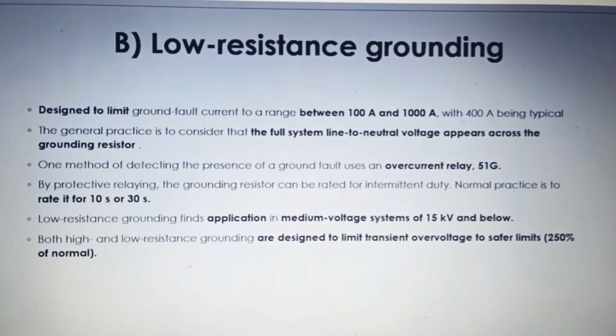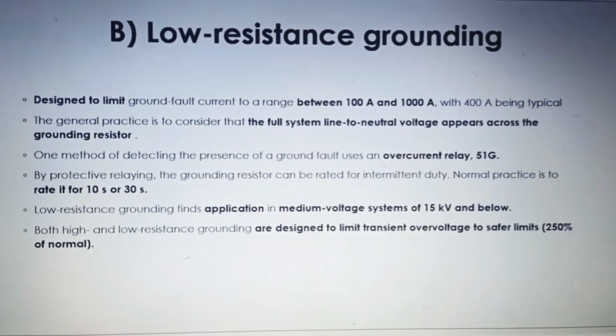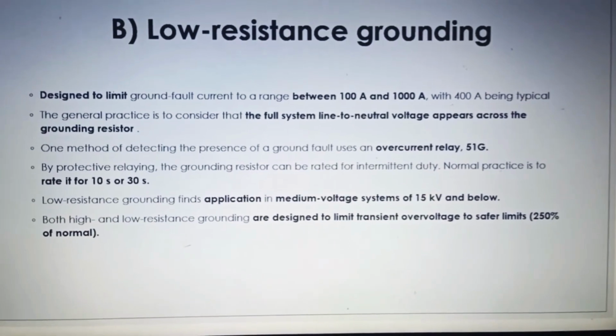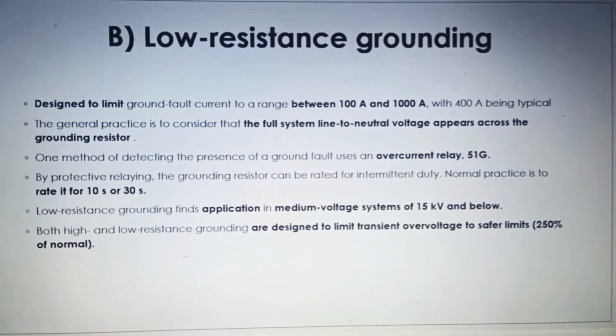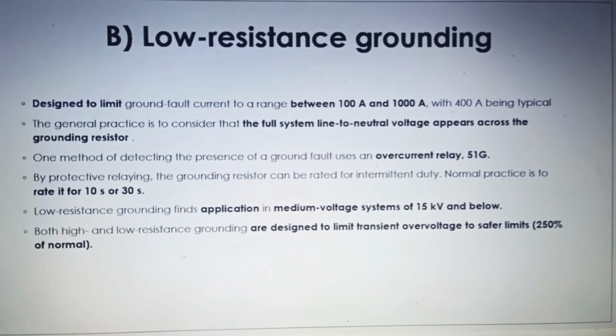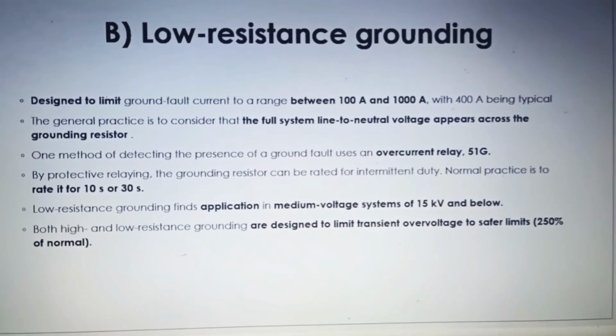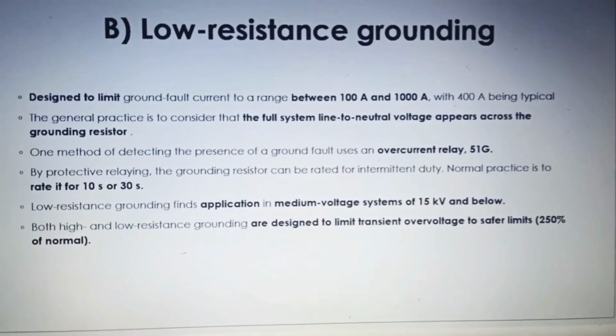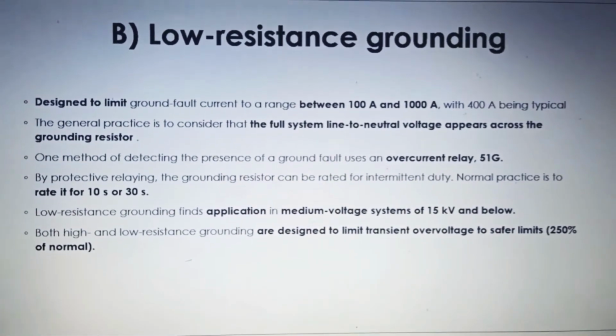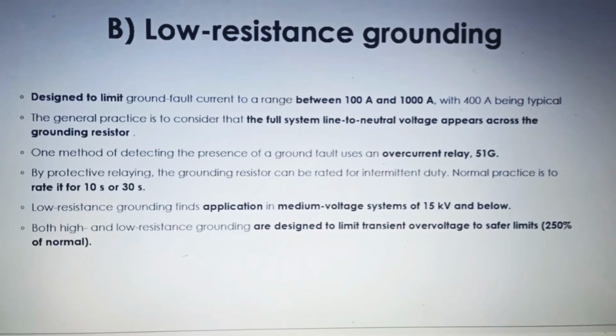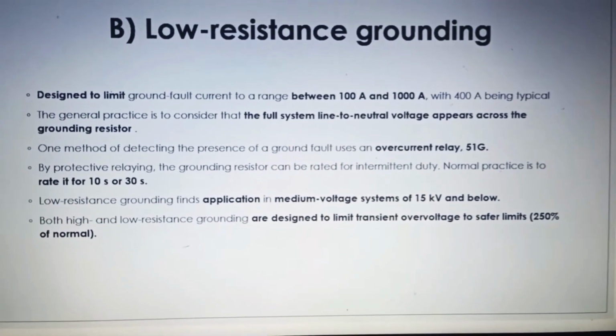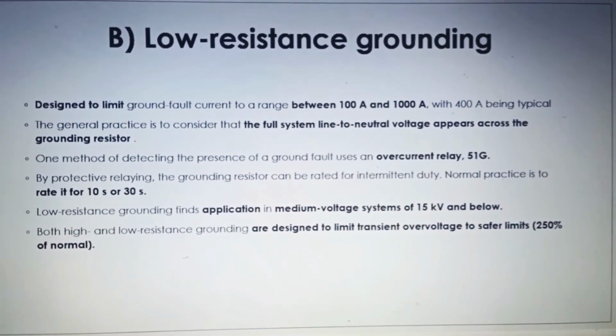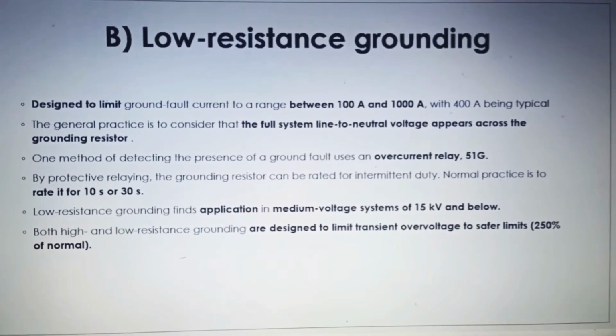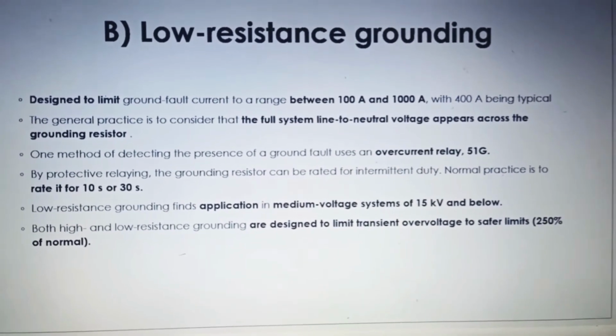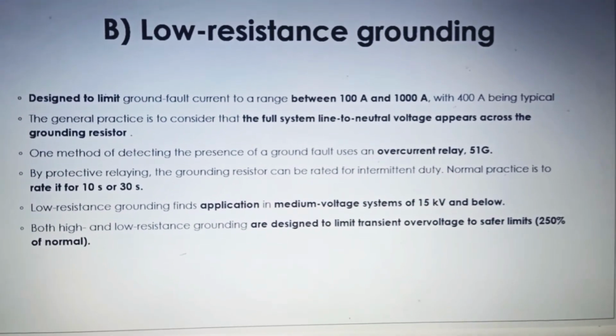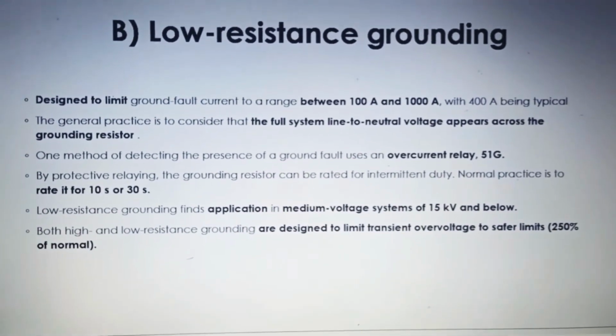Low resistance grounding finds application in medium voltage of 15 kilovolts and below, particularly where large rotating machinery is used. By limiting the ground fault current to 100 amperes instead of 1000 amperes, damage to expensive equipment is reduced. A special application of low resistance grounding is also mandated in mining systems supplying portable equipment, drilling cables. Both high and low resistance grounding are designed to limit transient overvoltage to a safer limit, let's say 250% of normal.